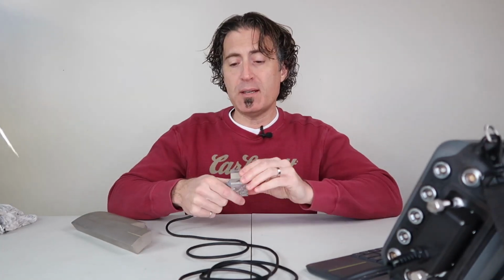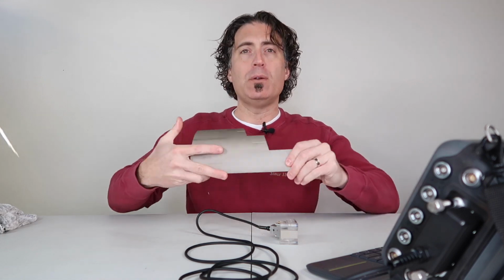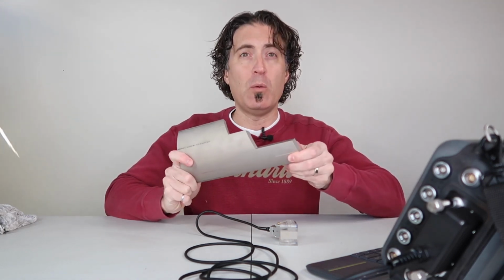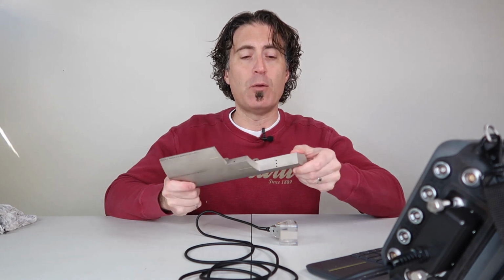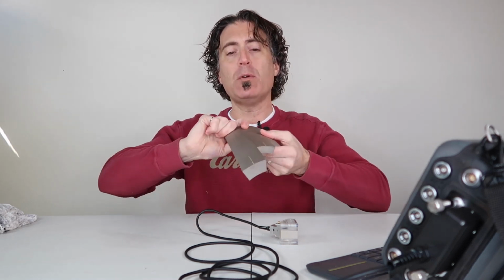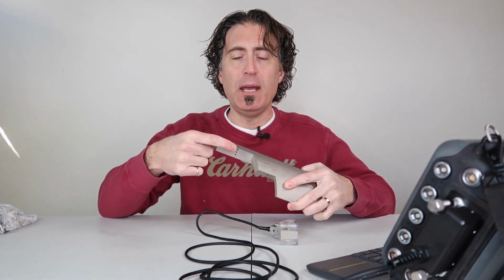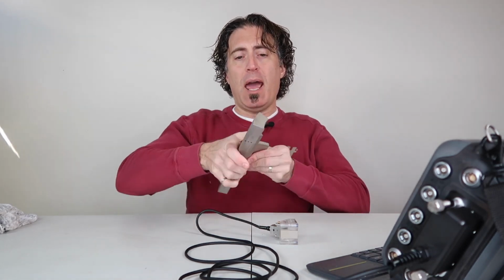a TCG. The equipment I'm going to be using, this is a 5 MHz 32 element probe, and I'm going to use this 6 to 10 inch ERVW or extended range variable wall calibration block. This is for ASME piping welds, and I'm going to use the 23 millimeter step on the end, which is the largest one. It has 3 holes in it, and if we look on the edge of the block, it will tell us that that's T3 or thickness number 3, which is 0.906 inches or 23 millimeters.